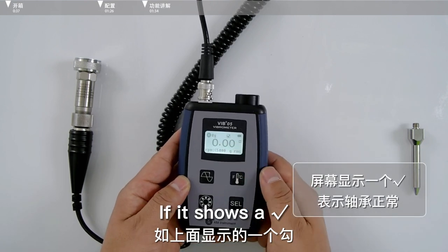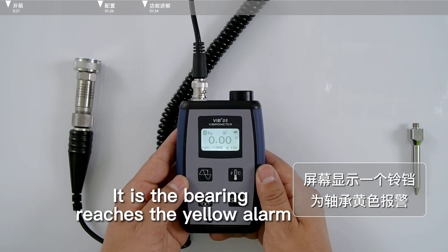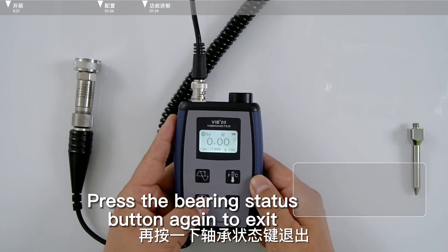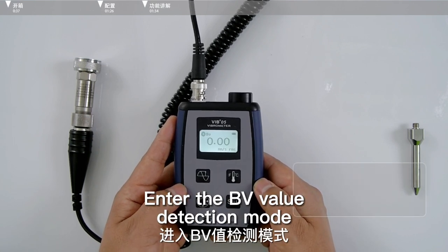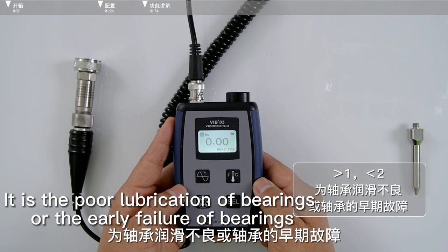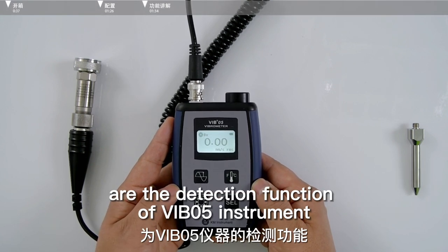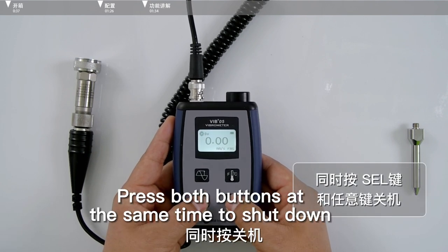Check the result: if a check mark appears, the bearing is normal. If one bell appears, the bearing has reached the yellow alarm level. Two bells indicates a bearing red warning. Press the bearing status button again to exit. Switch with the SEL key to enter BV value detection mode. A BV value less than 1 indicates a normal bearing condition. If the value is greater than 1 and less than 2, it indicates poor lubrication or early bearing failure. A value greater than 2 indicates a bearing fault. These three functions — vibration measurement, infrared temperature, and bearing state detection — are the detection functions of the VIB05 instrument. After testing, press SEL and any key simultaneously to shut down.